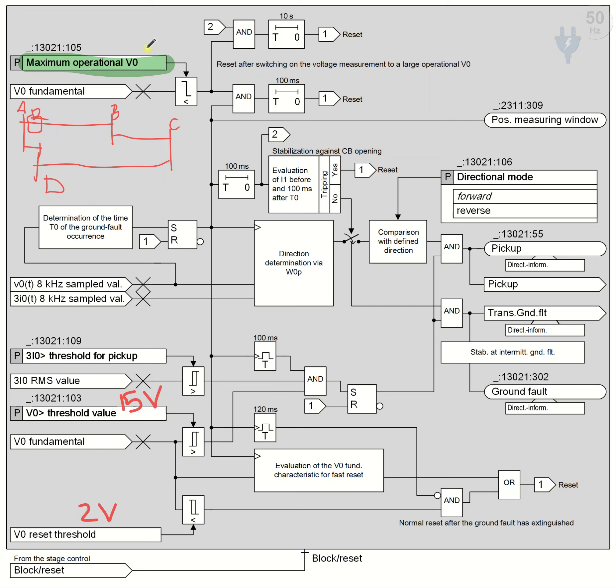For further discussion: in the case of a mesh or ring system, if V0 from calculation or measurement is greater than 2.5 volts, we take that V0 value and multiply it by 1.2. This result is then set as the maximum operational V0. So the maximum operational zero sequence voltage for a ring system = V0 × 1.2.